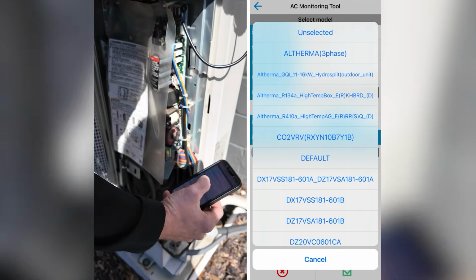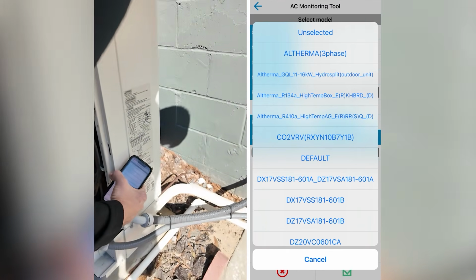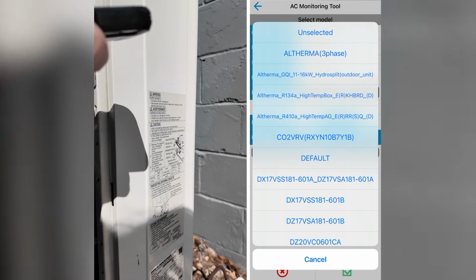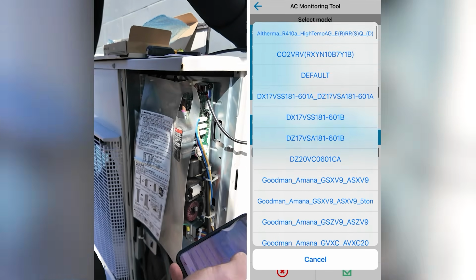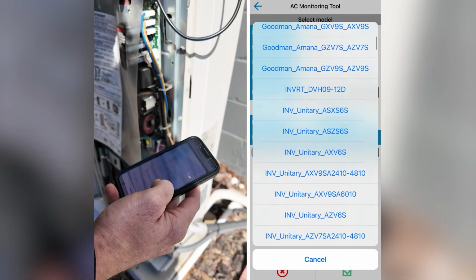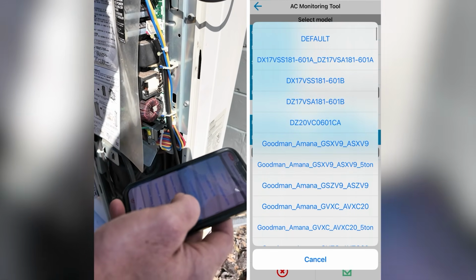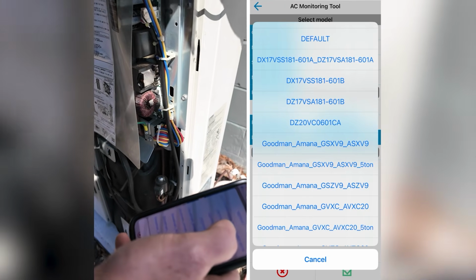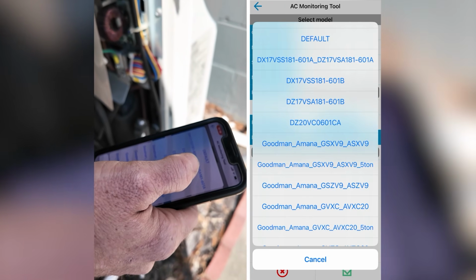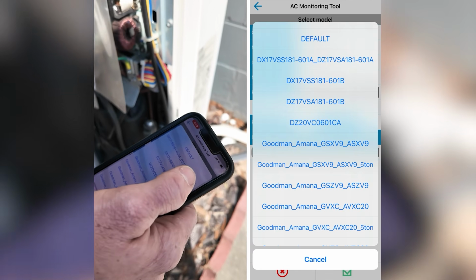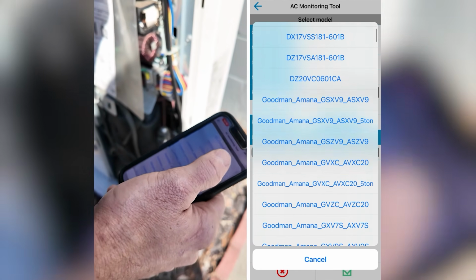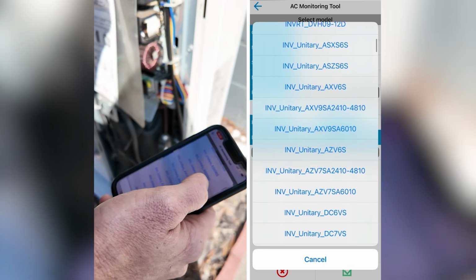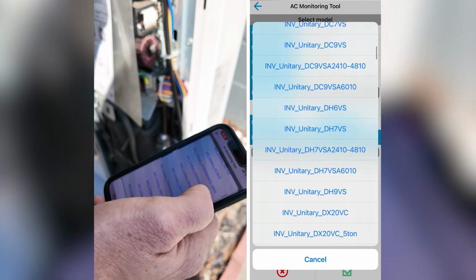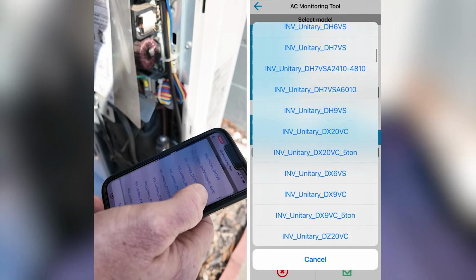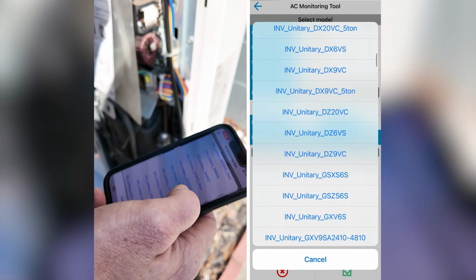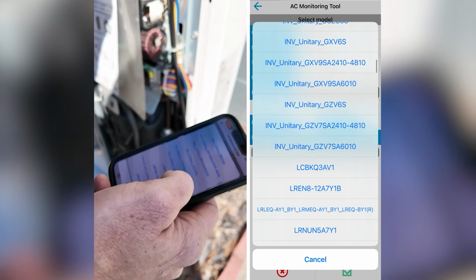So if we go down to the model number down here, we'll see that this is a DZ6 VSA. And so we're going to go in here and see if we can find something that is remotely similar. We're going to pick the, right there, DZ17 VSA. Now the model number may not be exactly specific to what you're looking for, but it's the series that counts. You'll notice that this list isn't exactly up to date with the latest and greatest. But you want to make sure that if you can't find the exact model, you find something within the same range. Inverter unitary is the right category that we're looking for.